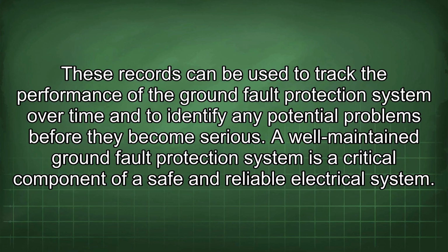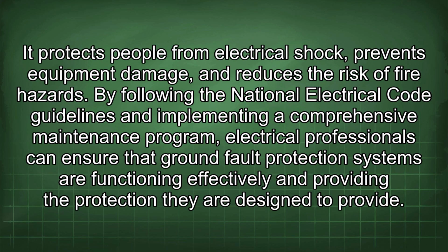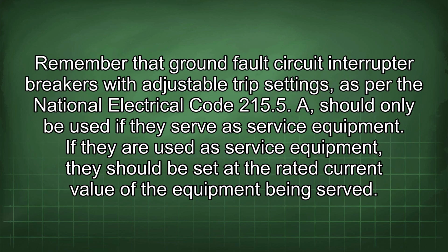A well-maintained ground fault protection system is a critical component of a safe and reliable electrical system. It protects people from electrical shock, prevents equipment damage, and reduces the risk of fire hazards. By following the National Electrical Code guidelines and implementing a comprehensive maintenance program, electrical professionals can ensure that ground fault protection systems are functioning effectively and providing the protection they are designed to provide. Remember that ground fault circuit interrupter breakers with adjustable trip settings, as per the National Electrical Code 215.5, should only be used if they serve as service equipment. If they are used as service equipment, they should be set at the rated current value of the equipment being served.